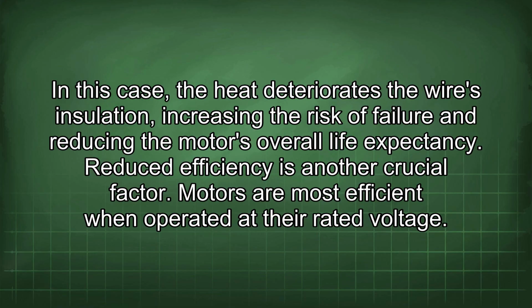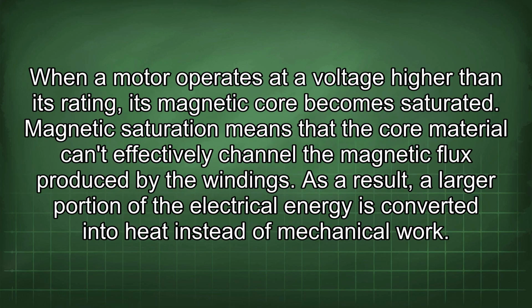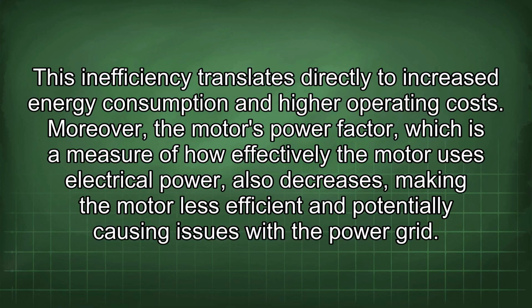Motors are most efficient when operated at their rated voltage. When a motor operates at a voltage higher than its rating, its magnetic core becomes saturated. Magnetic saturation means that the core material can't effectively channel the magnetic flux produced by the windings. As a result, a larger portion of the electrical energy is converted into heat instead of mechanical work. This inefficiency translates directly to increased energy consumption and higher operating costs. Moreover, the motor's power factor, which is a measure of how effectively the motor uses electrical power, also decreases, making the motor less efficient and potentially causing issues with the power grid.